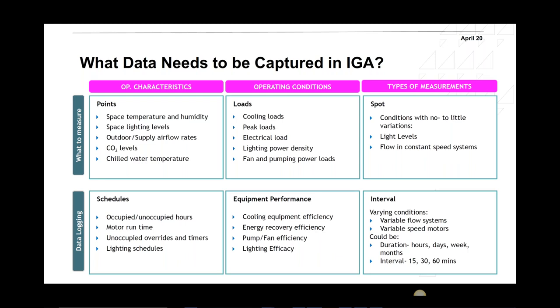Normally, I would leave that for at least a month to see what's happening under different weather conditions. Energy recovery efficiency: if I have a fresh air handling unit or an outdoor air handling unit with a heat recovery wheel, I can take the temperatures before and after the wheel on the exhaust side and on the outside air side, to see the energy recovery efficiency compared to the catalog value and how much it's doing, whether it's worth changing or maybe cleaning it, and what the issue is with that particular heat recovery wheel and why it is not performing properly.